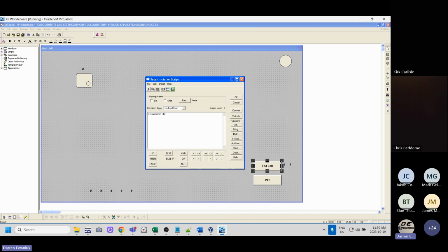I'm going to set that to 10. So 10 is the ENDC or end call function. So that ends whatever this master is connected to. So I want to make the second register the master number. So that's master 1, command 2 equals 1. Master 1, command 3. The only thing I need is an end call on the master number, so the rest of the arguments I can fill in with zeros. Master 1, command 5 equals 0.